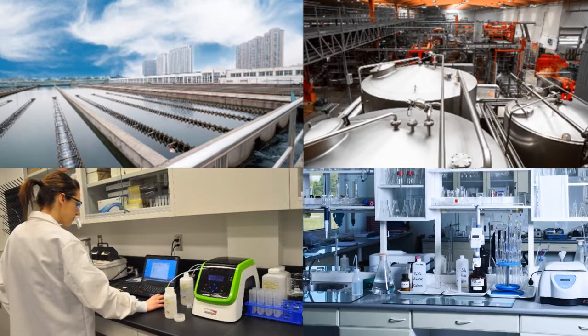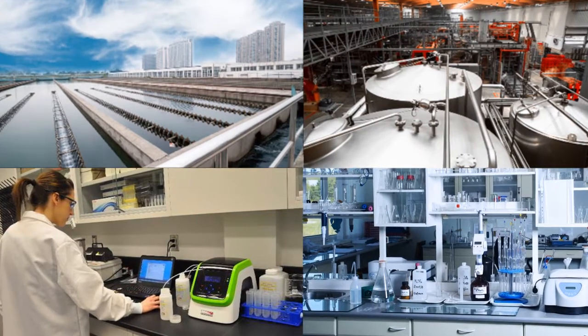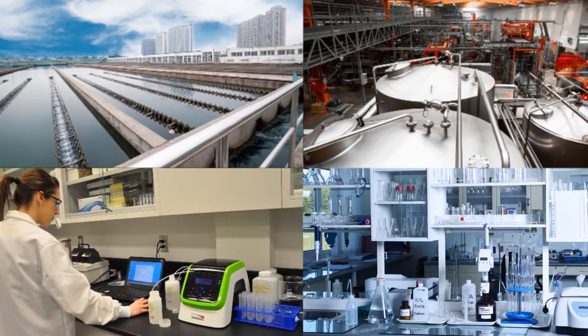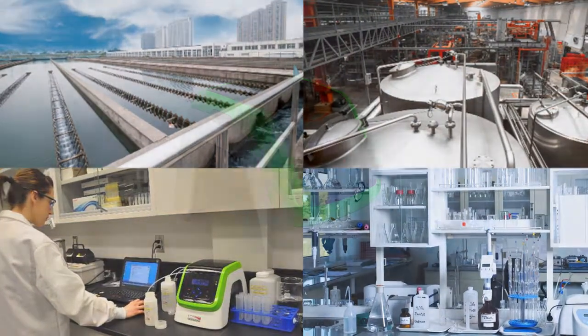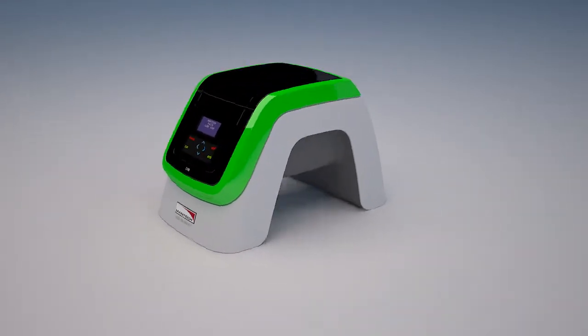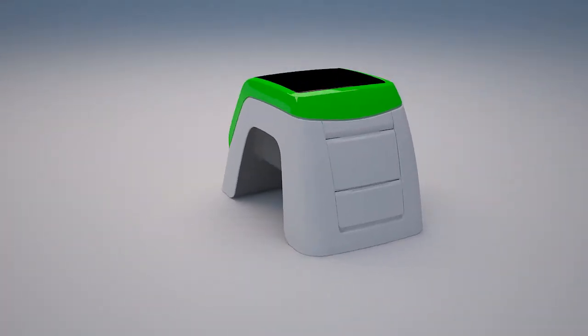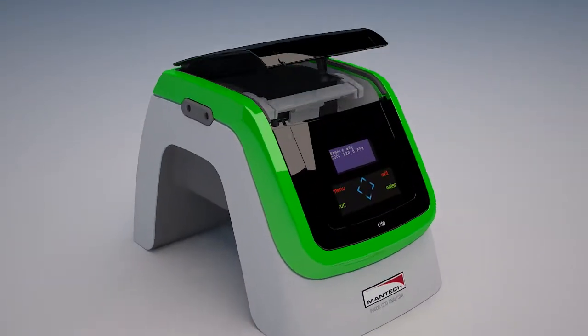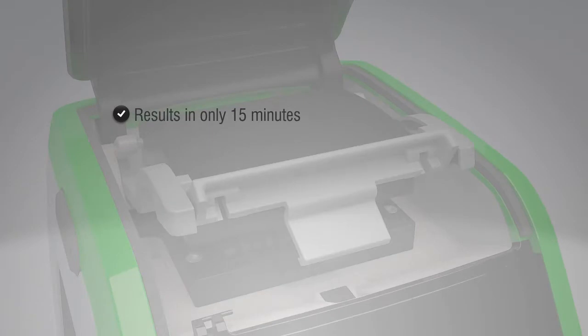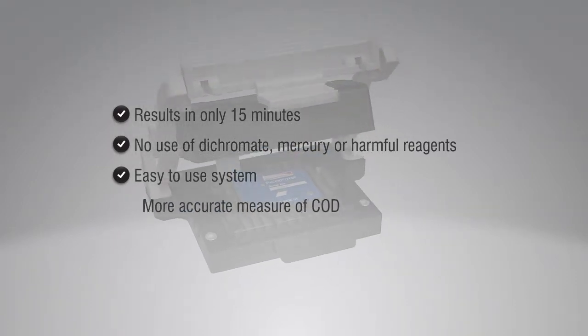The COD analysis technology is ideal for municipal wastewater treatment management plants, industrial facilities, academic institutions, and laboratories. The PeCOD nanotechnology-based approach to COD analysis overcomes the limitations and safety concerns of traditional dichromate-based methods. Results in only 15 minutes. No use of dichromate, mercury, or harmful reagents. Easy-to-use system. More accurate measure of COD.